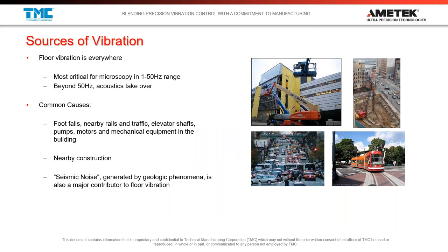So sources of vibration is pretty intuitive. It's just something you don't think about very often. And the thing about vibration is that it's everywhere. And what we're also finding is that particularly if you have a microscope, it's the low frequency range. And we also find that low frequency can also be a problem for a lot of photonics applications. It just depends on what types of resonances are in the components of your system. Once you start getting into higher frequencies, we start seeing acoustics taking over. So floor vibration is going to have an impact on your instrument between 1 and probably 30 to 50 hertz.